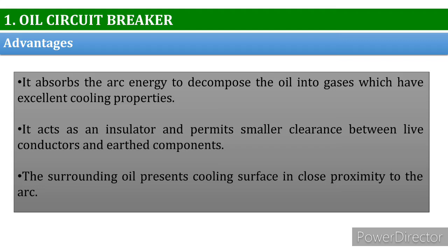The second one is it acts as an insulator and permits a smaller clearance between live conductors and earth components. The third one is the surrounding oil presents a cooling surface in close proximity to the arc. So these are the three advantages of the oil circuit breaker.